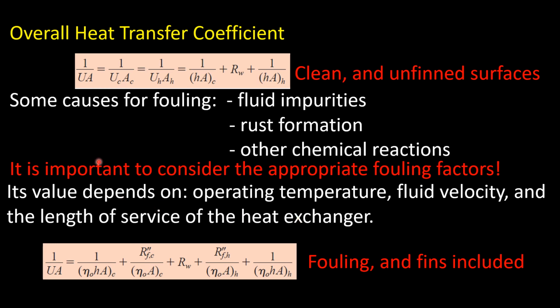Like here in our pictures, we only saw the fouling, for example, that was deposited by the exhaust gas. We would have had to cut open the heat exchanger and take a look inside to see what was deposited on the other side of the surfaces where the engine coolant is traversing the heat exchanger.